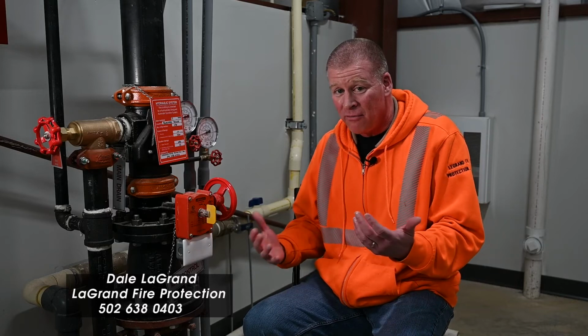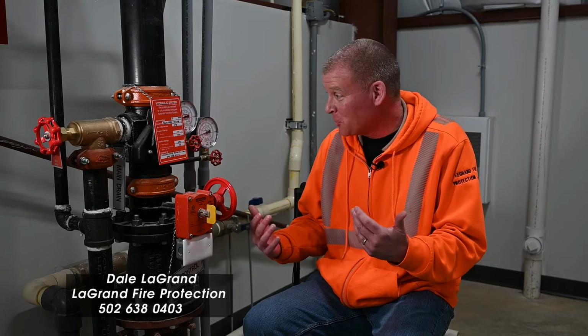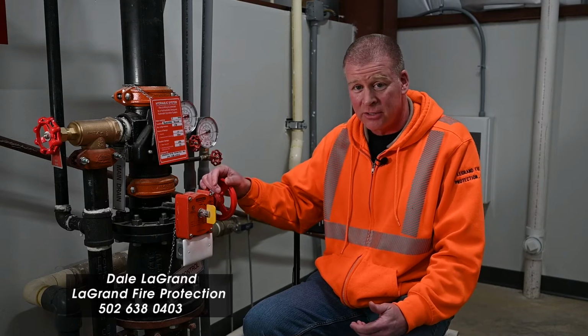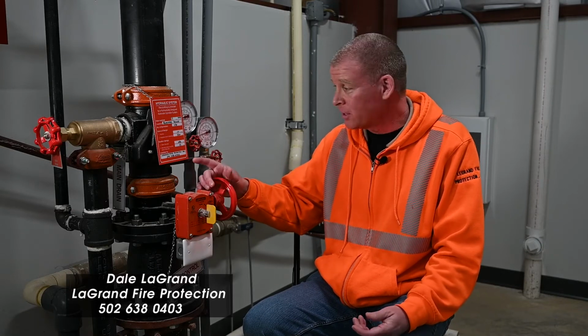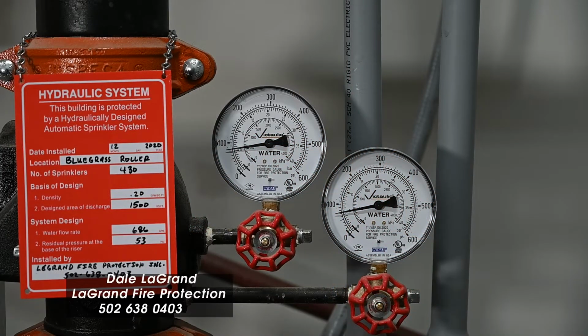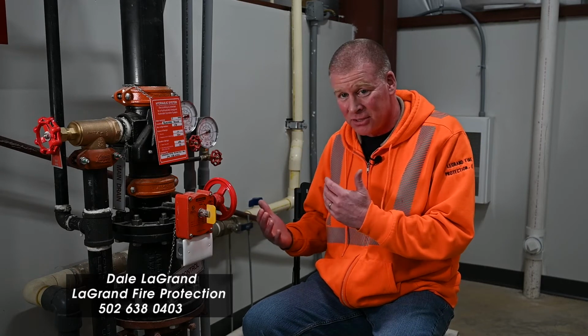As far as maintenance, you don't really have to do anything to the sprinkler system. If you have an issue, you need to call a fire protection contractor, preferably us since we put it in. Our information's here, 502-638-0403, LeGrand Fire Protection. The other thing you want to do on a weekly basis is check these gauges. You might put a black mark on the gauge where it is now, and if it drops more than 10%, that could indicate something's happened with your underground, and you might want to have us come and check it out, or at least give us a call so we can see what's going on.